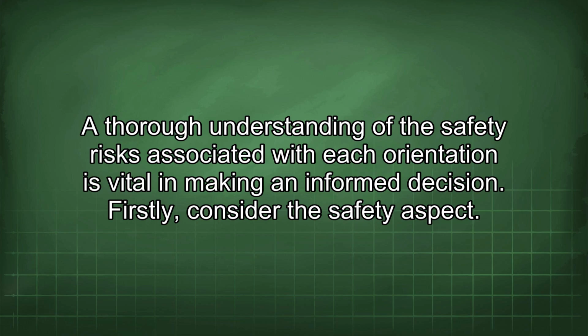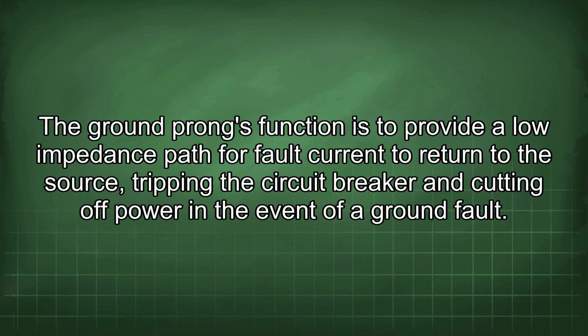Firstly, consider the safety aspect. The ground prong's function is to provide a low impedance path for fault current to return to the source, tripping the circuit breaker and cutting off power in the event of a ground fault.